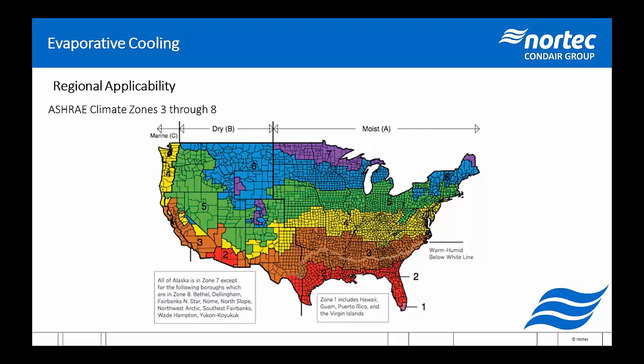That being said, the cooler and drier it is, the higher the humidification load is typically, and we'll see more benefit there, or the hotter and drier it is. So that would be, again, yes, Phoenix, San Diego, potentially. I've done analysis in Toronto and Minneapolis as well that comes up with quite significant energy savings compared to either mechanical cooling or mechanical cooling and steam humidification. However, if you're in the southern tip of Florida or somewhere near Miami, there's a lot less we can do with humidification.